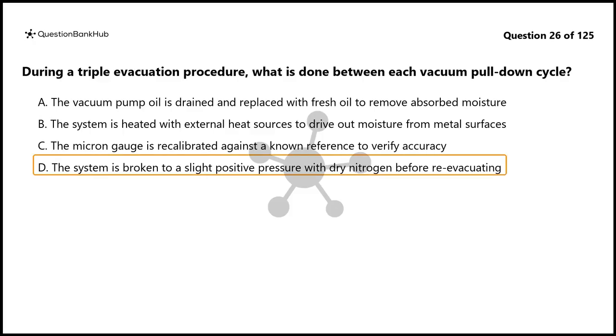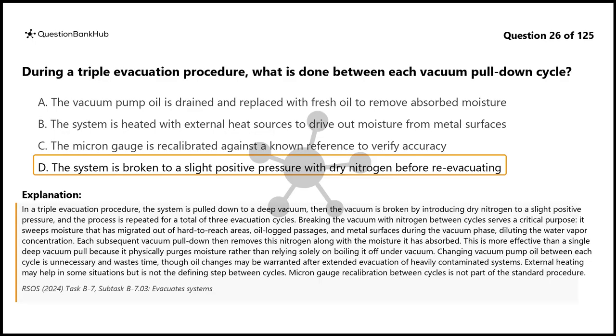The correct answer is D. In a triple evacuation procedure, the system is pulled down to a deep vacuum, then the vacuum is broken by introducing dry nitrogen to a slight positive pressure, and the process is repeated for a total of 3 evacuation cycles. Breaking the vacuum with nitrogen between cycles serves a critical purpose. It sweeps moisture that has migrated out of hard-to-reach areas, oil-logged passages, and metal surfaces during the vacuum phase, diluting the water vapor concentration. Each subsequent vacuum pull-down then removes this nitrogen along with the moisture it has absorbed.